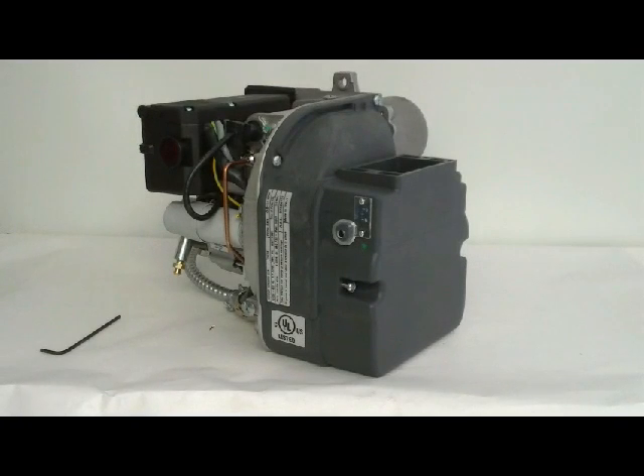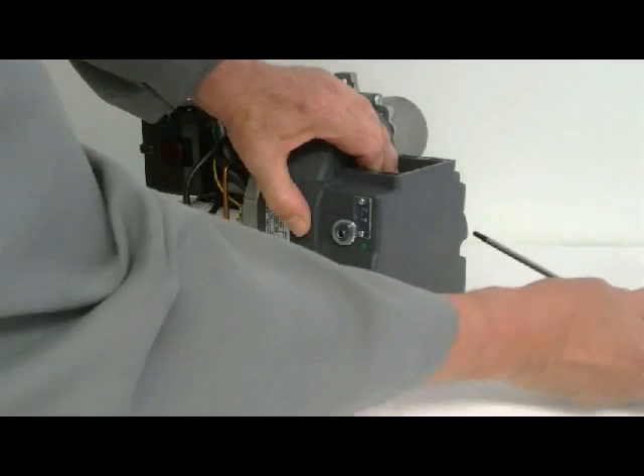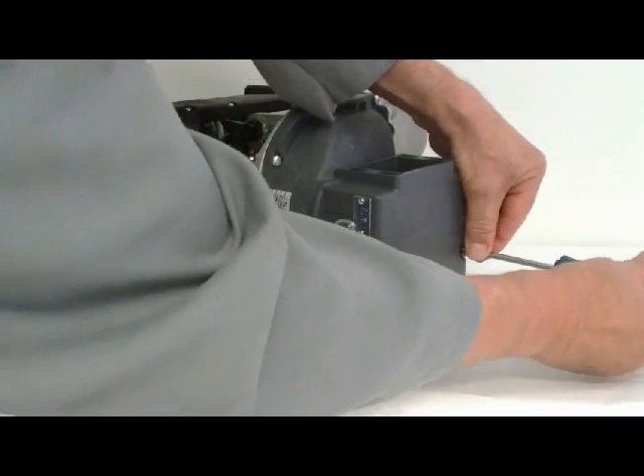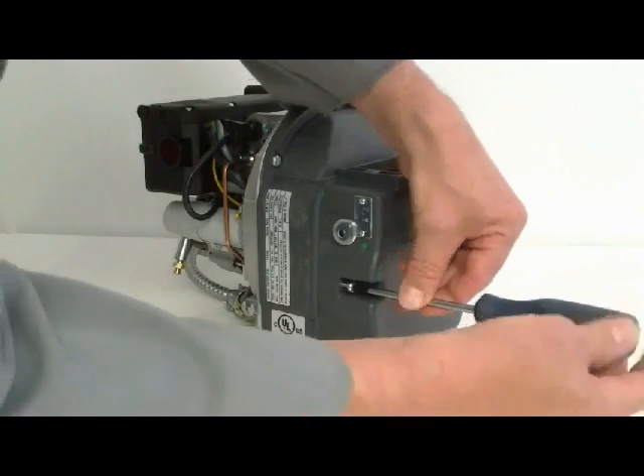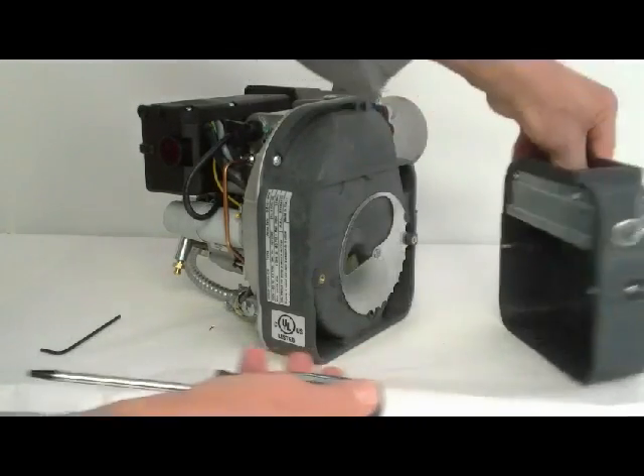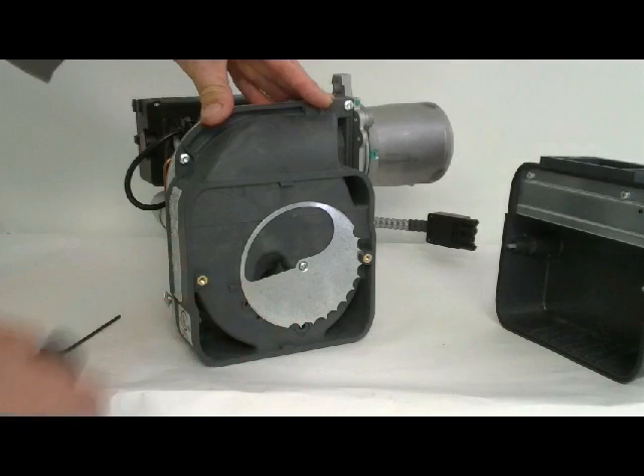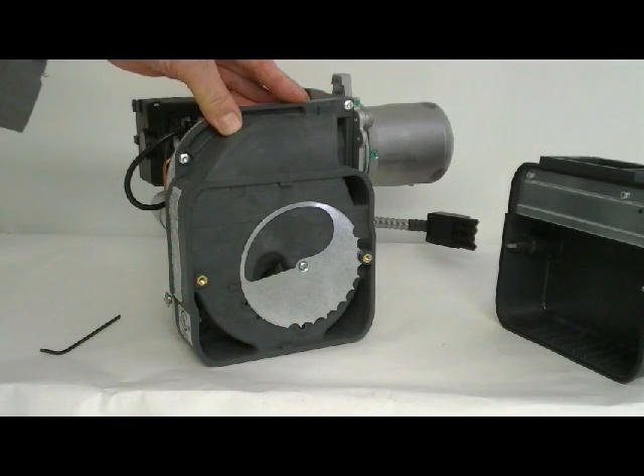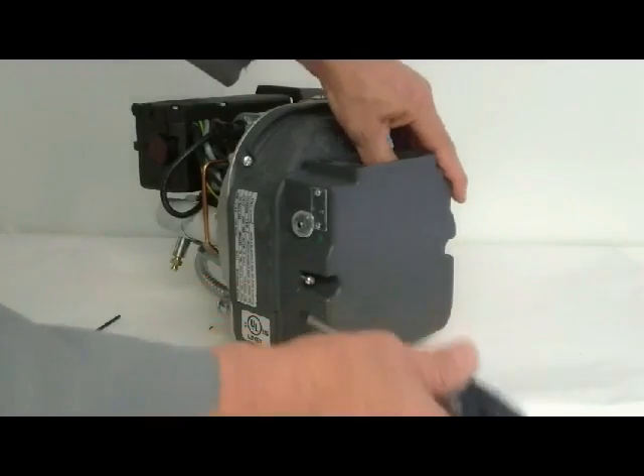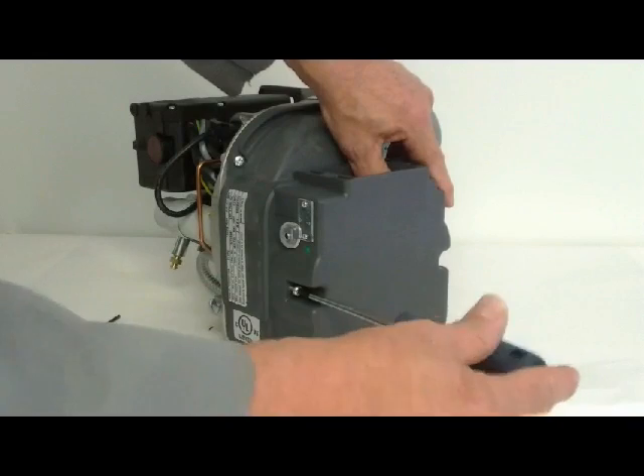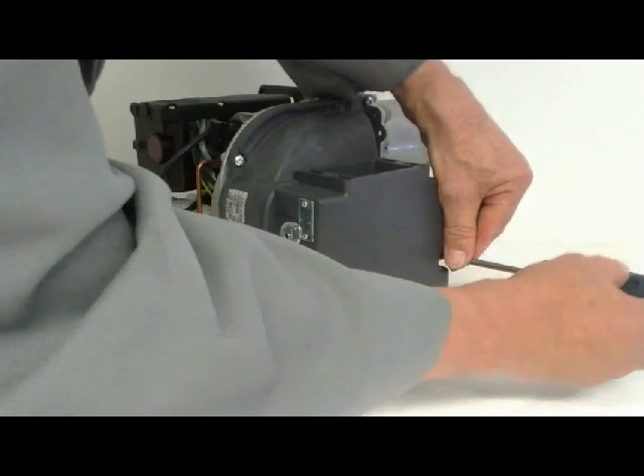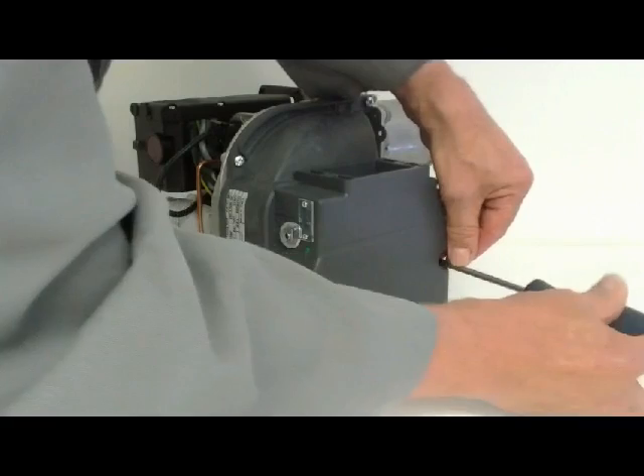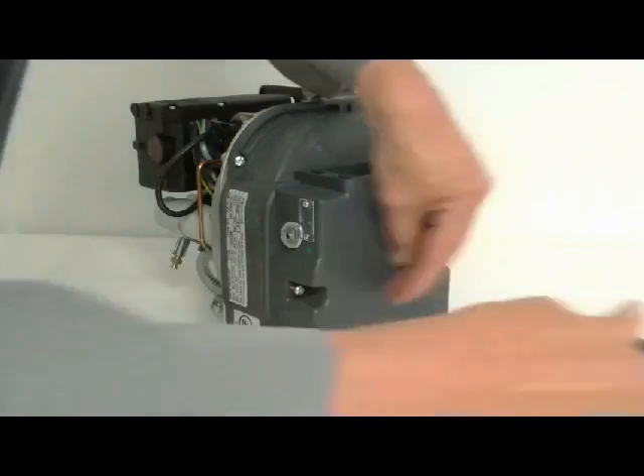There are two air adjustments to be made on the RDB burner. The main air damper is located beneath the air cover. Remove the air cover using a T25 Torx screwdriver. Loosen the screws on either side. Remove the cover. The position of this damper is determined by the firing rate of the burner. It is made before the burner is assembled on the boiler. Re-secure the air cover.